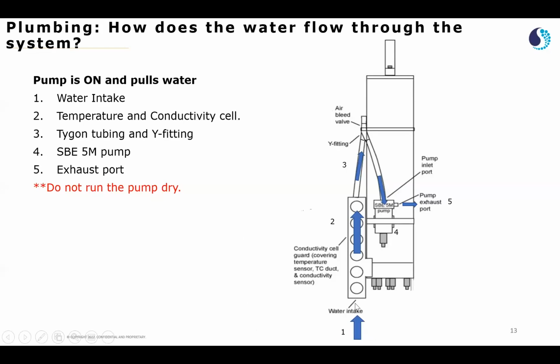Let's go through the diagram step by step. The first step is where the water goes through the intake system here at the conductivity guard cell. So the outermost layer would be the guard cell, and inside the guard cell we have the temperature probe first, and then we have the conductivity cell. So the water goes through the system into the Y fitting and this Tygon tube, and then it flows through the pump and out to the exhaust.